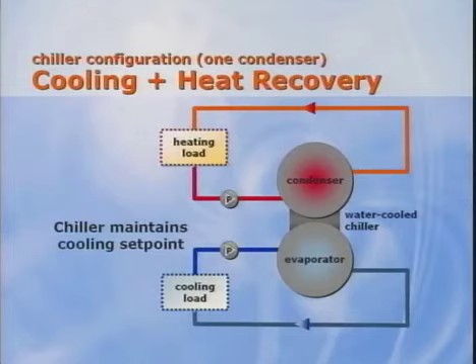In some cases, this standard chiller configuration can be used for heat recovery. The chiller's primary mission is to provide chilled water at the design set point. The chiller controls modulate compressor capacity based on the temperature of the water leaving the evaporator. The amount of heat produced by the chiller is determined by the cooling load and may be more or less than the heating loads require. The chiller can only be operated in this configuration when the need for heat exceeds the heat output of the chiller.